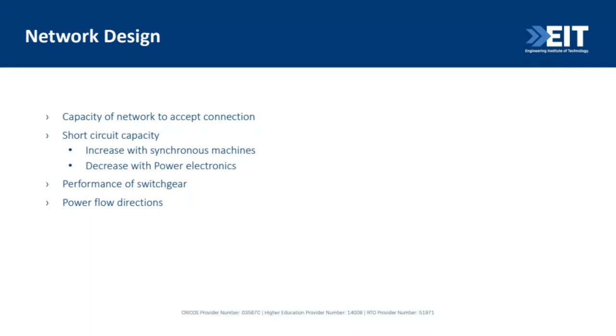For network design, there must be sufficient network capacity to accept connections, considering short circuit capacity especially when you increase synchronous machines or decrease power electronics. What is the performance of switch gear, and how will the power flow?